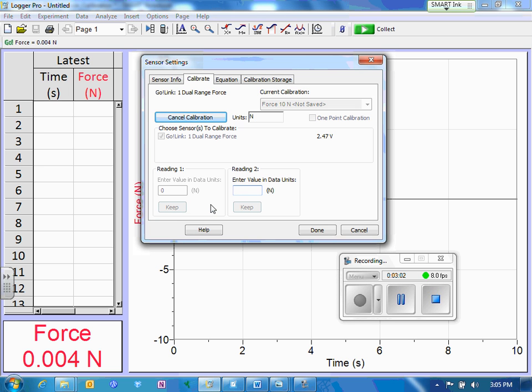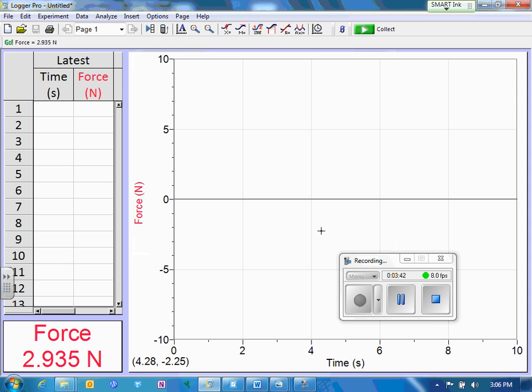The next value we want to enter is a value of 2.94 newtons. To do that, we're going to put 300 grams of mass on the hook, which I've just done. We're going to enter the value 2.94 newtons, and then hit keep. Then we're going to hit the button on the lower right where it says done, because we're all done. And you notice that the force reading in the lower left corner is 2.94 newtons.